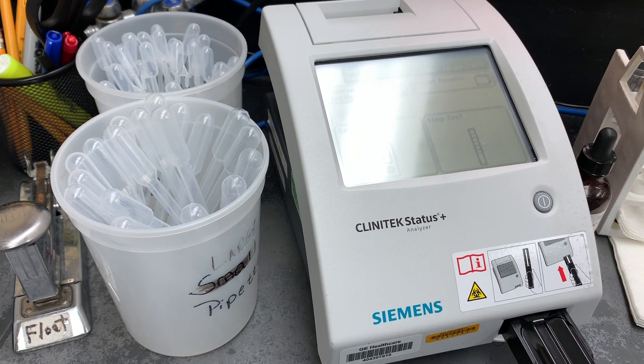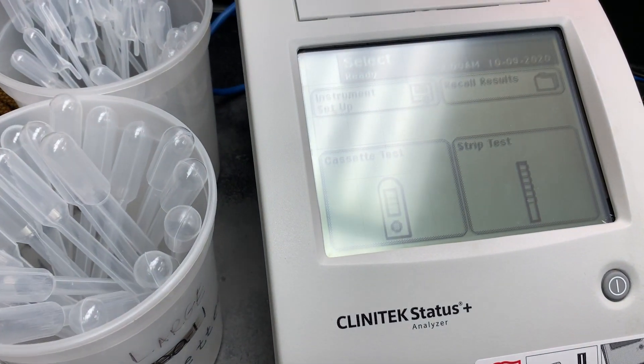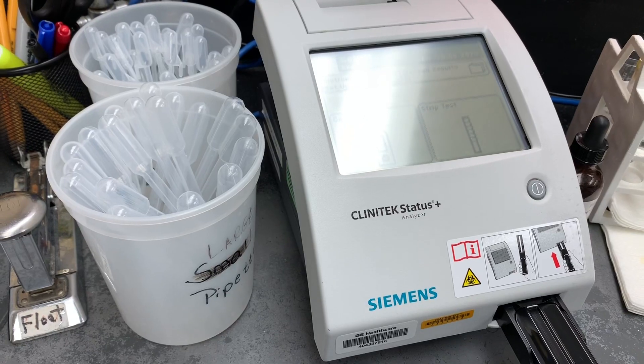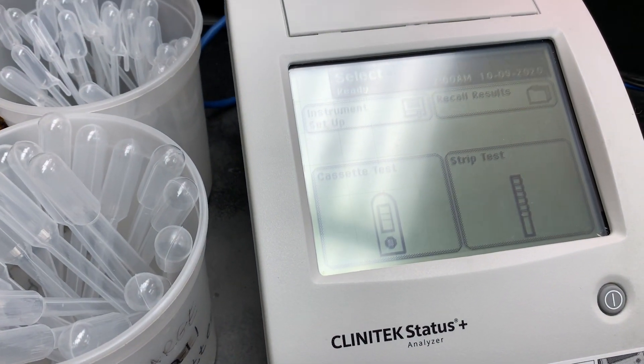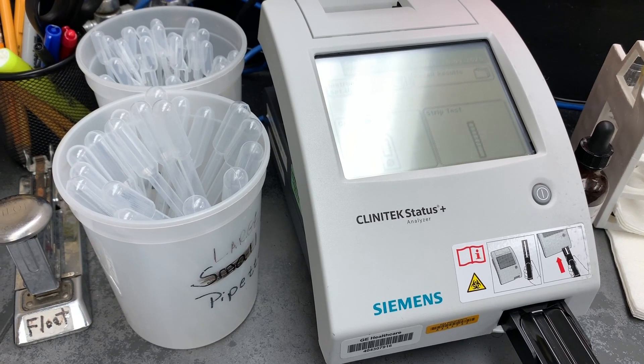This machine right here is the CLINITEK Status+ — this is a urinalysis machine. What we do is we take a strip, dip it in urine, put it on the analyzer, and then it reads it and gives off the results.